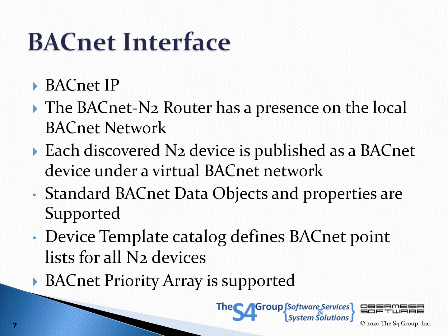From the standpoint of a BACnet client, it thinks it is talking with open BACnet devices. All details of the Metasys N2 protocol are handled by the S4 Open BACnet N2 router. Device ID and network can be set and easily modified via the management console. Virtual BACnet devices are assigned unique BACnet device IDs.